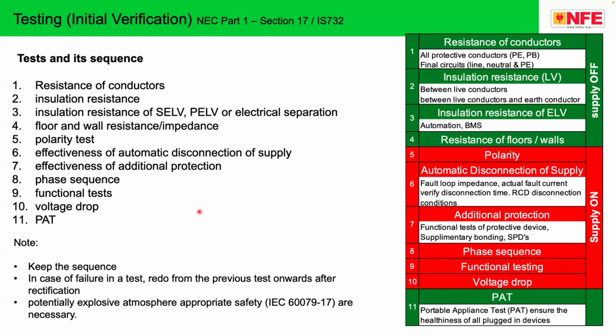There are several subjects to be tested during the initial verification, before using the appliance. You are supposed to conduct, let's say, serial number 1 to 10 tests, starting with the resistance of conductors, insulation resistance. You see number 6, effectiveness of automatic disconnection of supply, and so on. All these tests are made mandatory. There are formats provided in the standard. You must fill up the format.